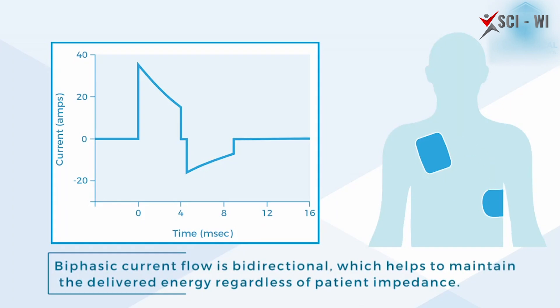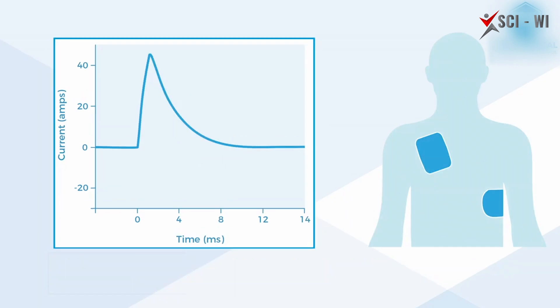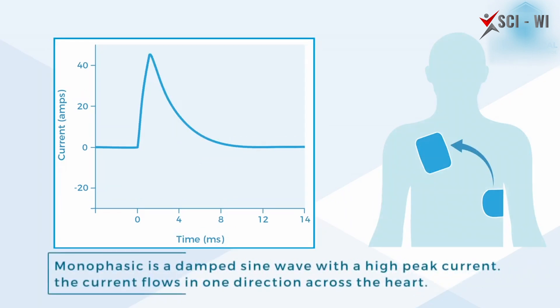There needs to be enough current to reach the heart in order to terminate the rhythm or fibrillation. At the same time, it is necessary to avoid excessively high peak current, which could damage the patient's heart.